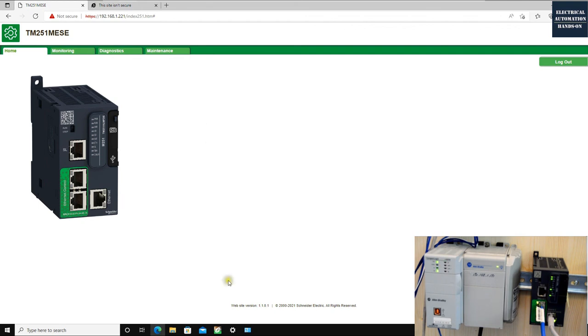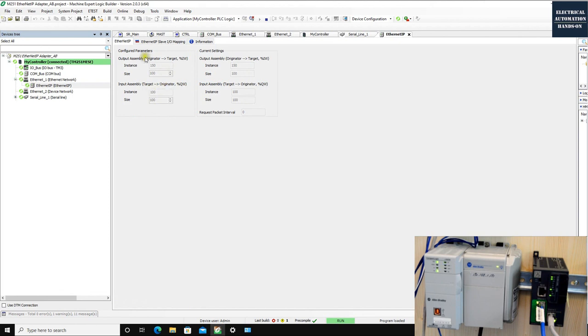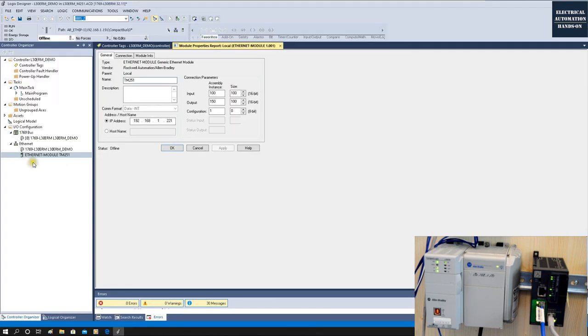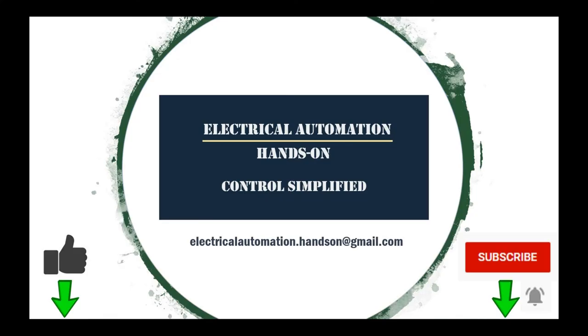In summary, this configuration is straightforward: on the Schneider side, add EtherNet/IP and configure the input and output assembly numbers. On the Allen-Bradley side, add a Generic EtherNet Module and manually configure the input, output, and configuration instance numbers — making sure the size matches the Schneider software setting. This completes the demonstration of EtherNet/IP communication between Allen-Bradley and Schneider TM251. Thank you for watching — if you liked this video, please give it a thumbs up, subscribe, and hit the bell.